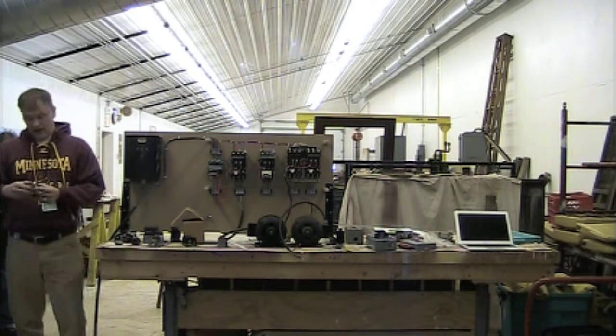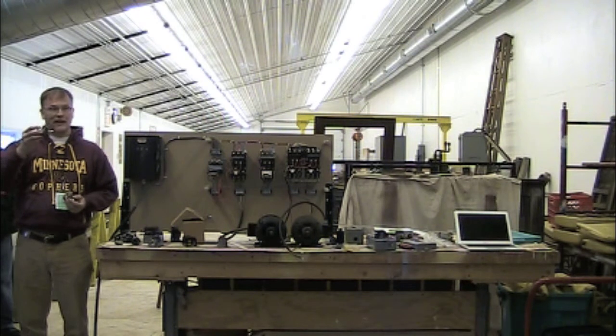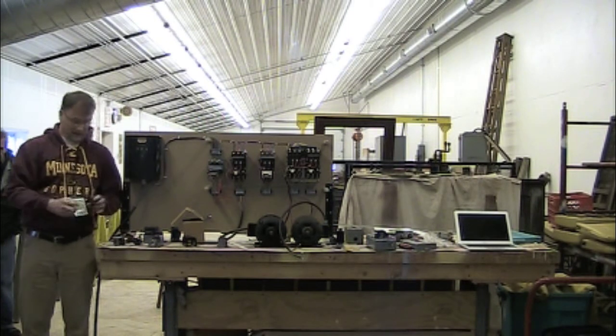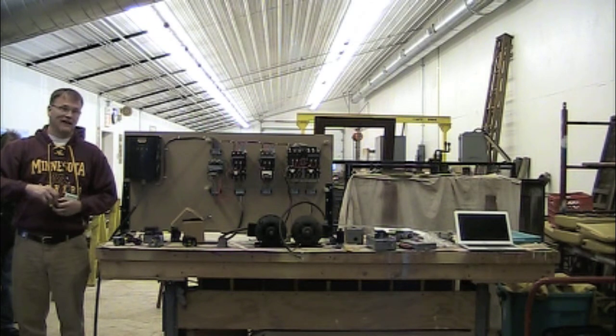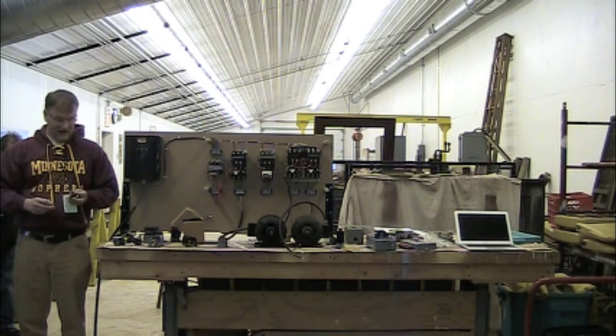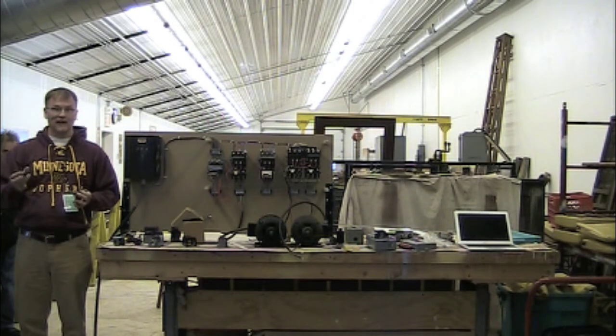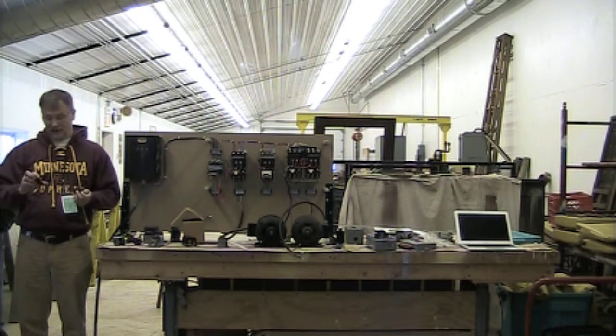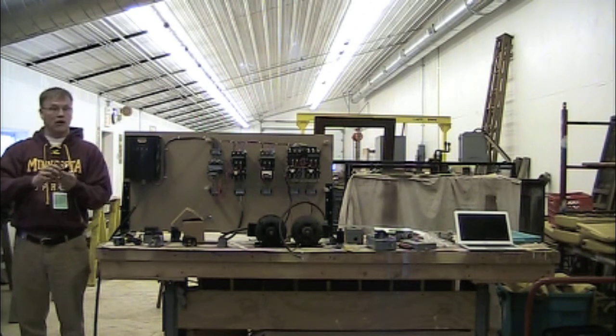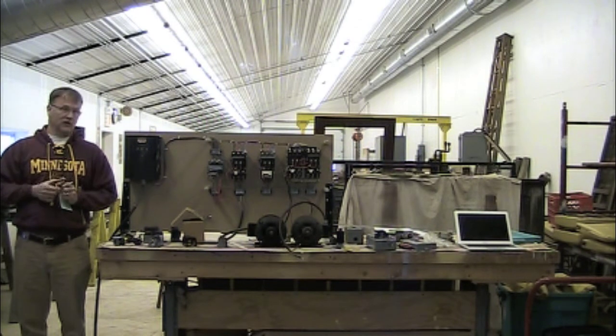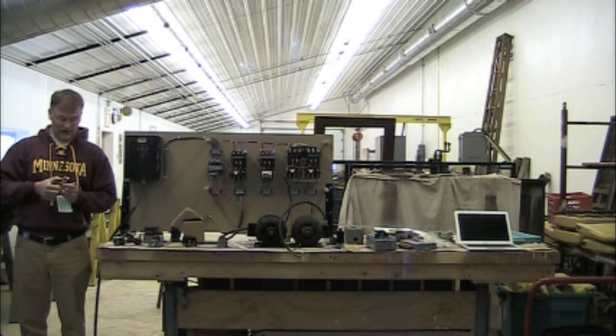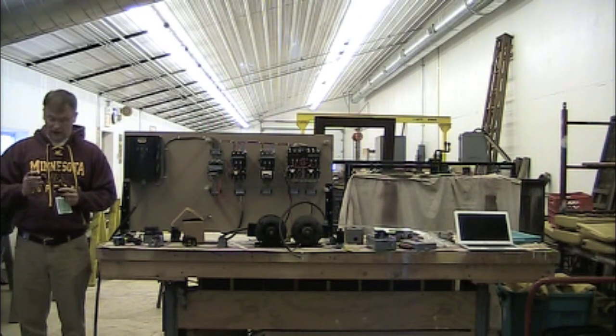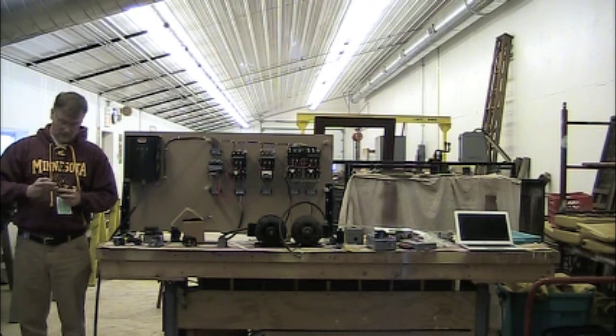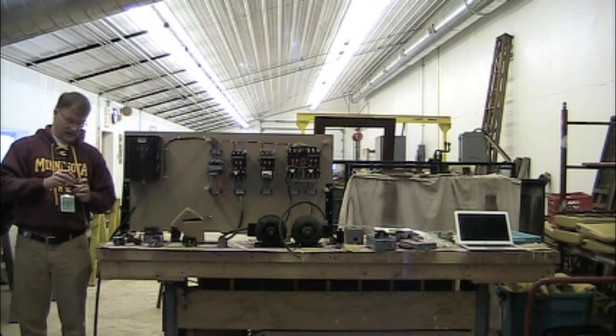But they're just a basic operator body. This has got nothing on it, and you can change the functionality of this by all the different contact sets you can buy to put on these. So if you're looking for these, a lot of times you look at the catalog numbers or what you find on eBay, you need to know all the little pieces that are married together and whether it actually has the functionality you want. So this is a push-pull operator. So it's a maintained contact, not just a momentary like you use on the start-stop. And so this, you can put a contact block set on it. And these all just screw right on the back. If my hands don't shake.